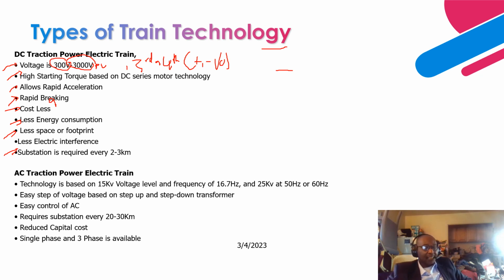Next is the AC traction power train. This technology is based on achieving 15 kV at a frequency of 16.7 Hz, utilizing a frequency converter that converts the nominal 50 or 60 Hz down to 16.7 Hz to cut down on the cost of conductors, equipment, and size.